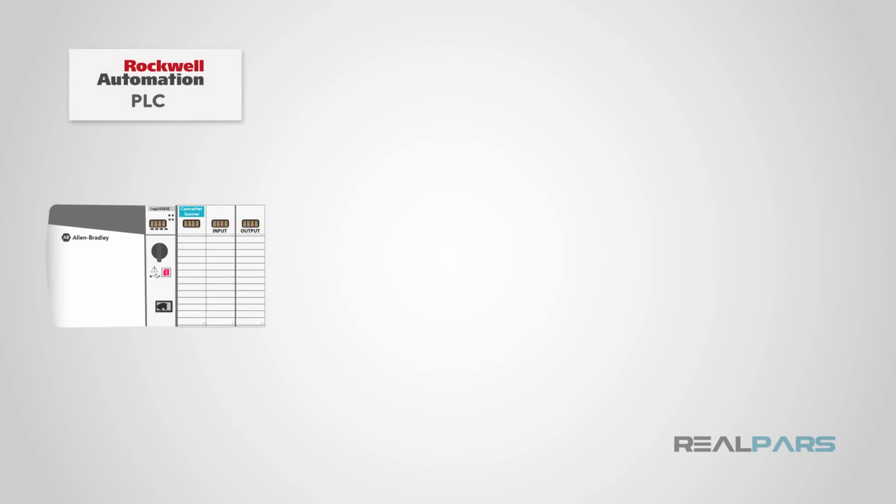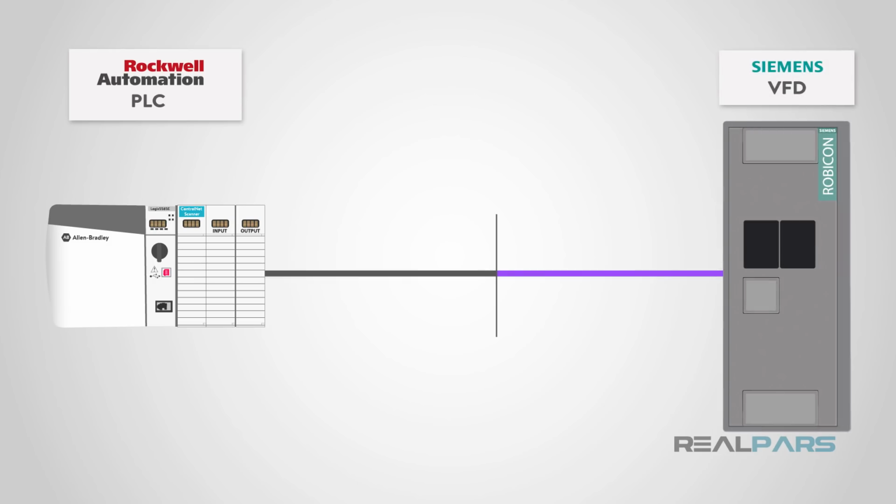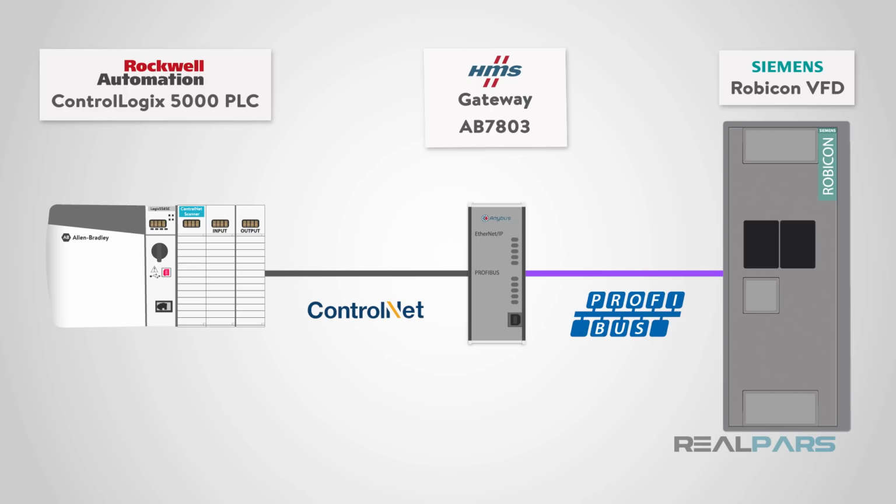Welcome to Part 2 of Rockwell ControlLogix PLC and Siemens VFD communication. As you have learned in the previous lesson, automation often requires communication between two heterogeneous systems from different manufacturers. In this video series, overall, we are communicating from a Rockwell Automation ControlLogix 5000 PLC using ControlNet network media with CIP protocol to a Siemens Robicon VFD using Profibus protocol, through a gateway converting ControlNet CIP protocol to Siemens Profibus protocol.